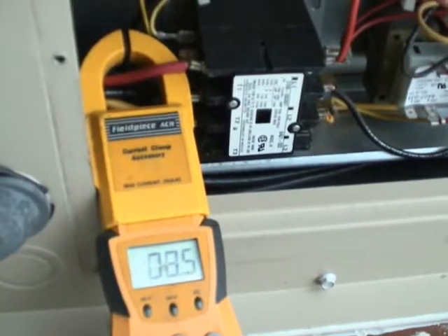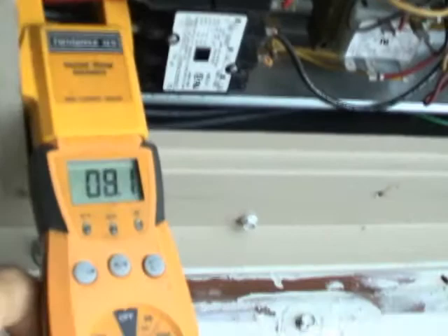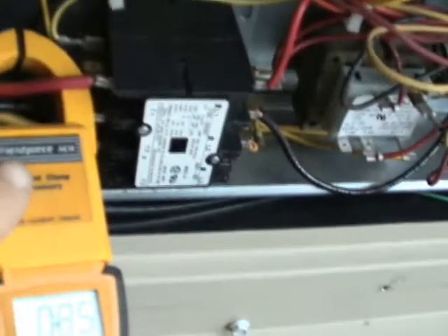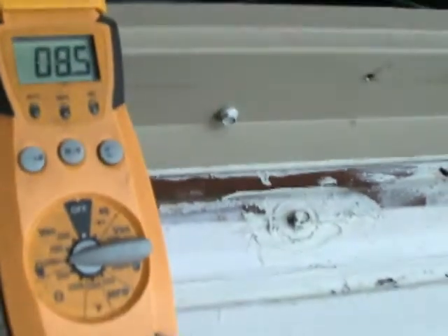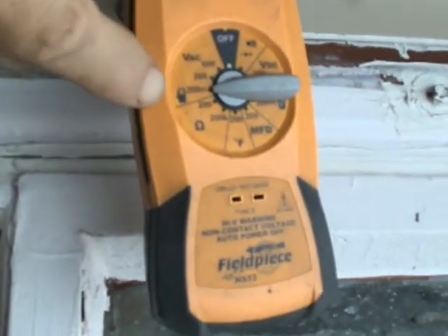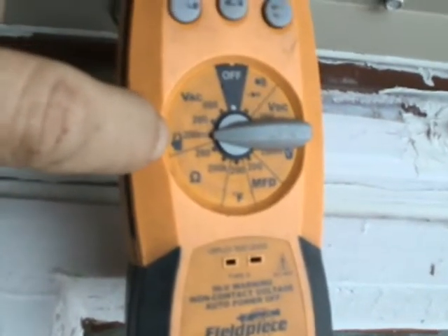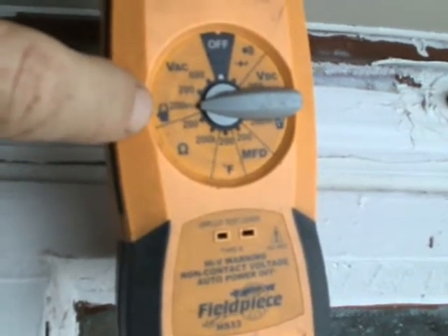What I do to measure an amp draw is I put my clamp on one leg of power coming out of the contactor that goes to the compressor. For example, here I'm reading 8.5, 8.4. I put my setting here — this little clamp meter right here — and the selector switch.